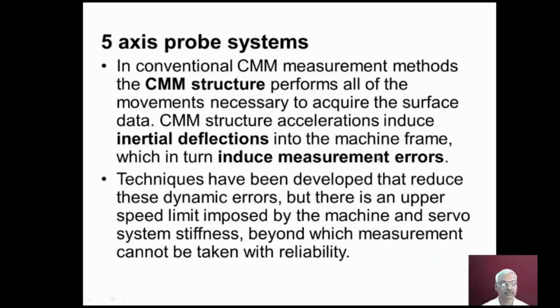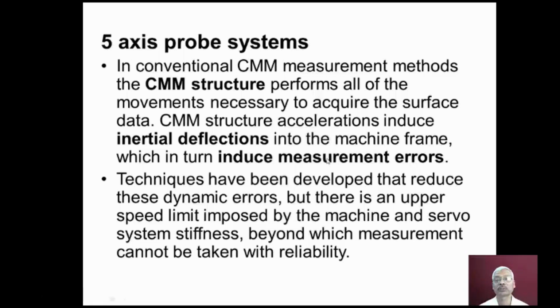Now let us discuss the 5-axis probe systems. In conventional coordinate measurement methods, the CMM structure performs all the movements, that is X, Y, Z movements necessary to acquire the surface data. CMM structure accelerations induce inertial deflections into the machine frame, which in turn induce measurement errors. Many techniques have been developed that reduce these dynamic errors, but there is an upper speed limit imposed by the machine and servo system stiffness, beyond which measurement cannot be taken with reliability.